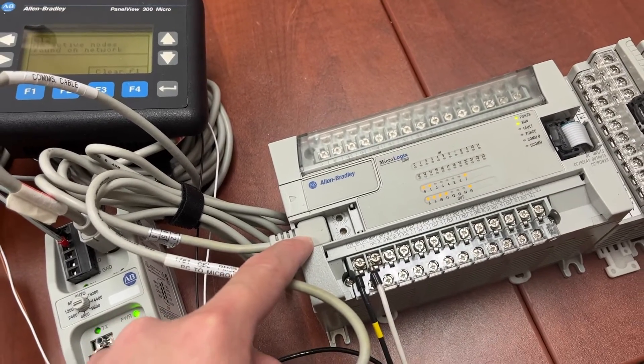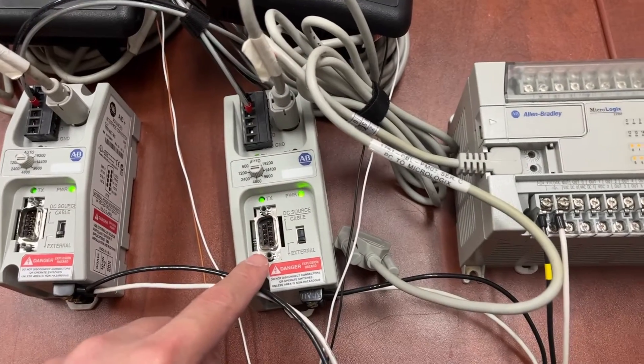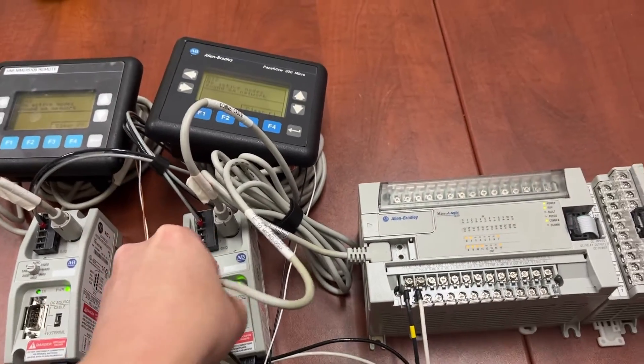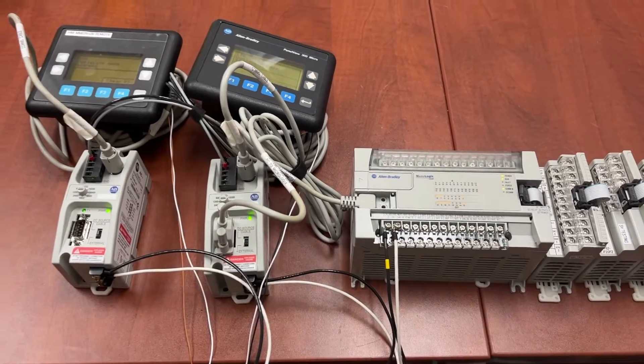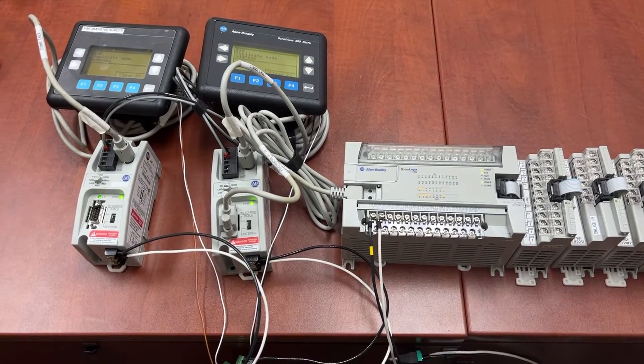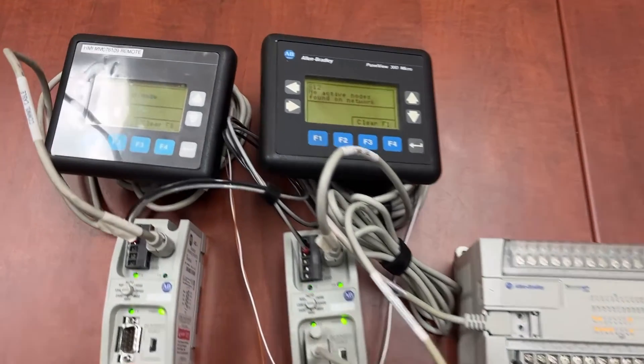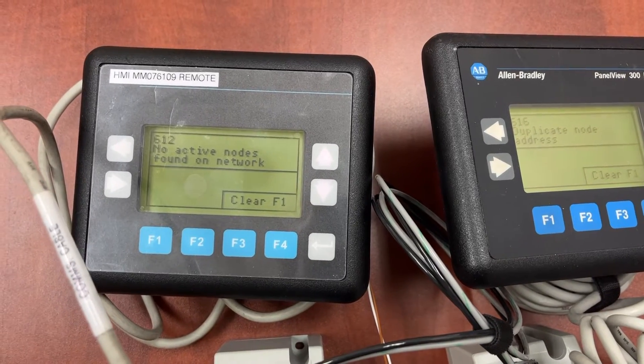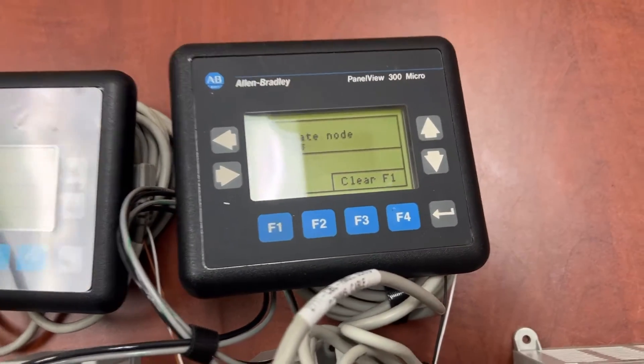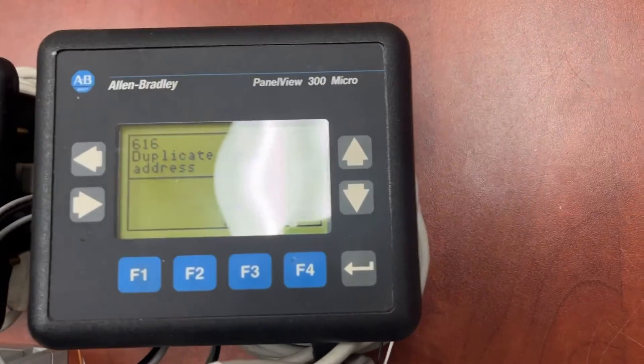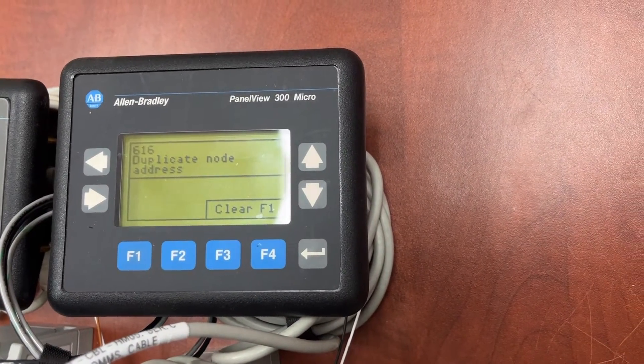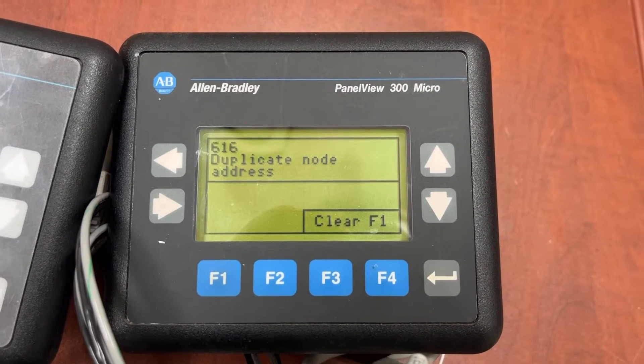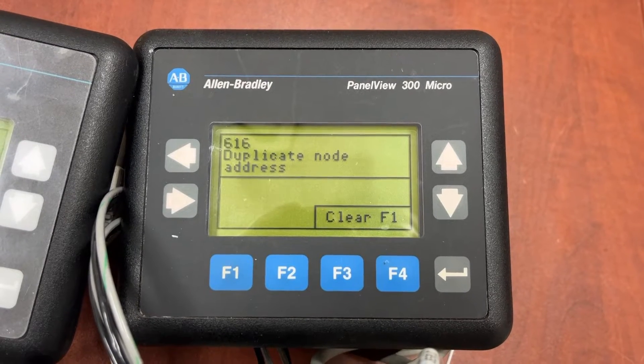The cable is 1761-CBL-PM02, with an 8-pin mini-DIN connector on one end and a 9-pin D-sub port on the other. We currently have two communication error messages on the HMIs: error 616 for duplicate node address and error 612 for no active node file on network.